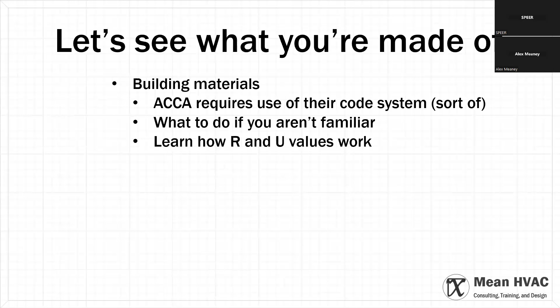So like I said, learn how U values work. Real simple, you just flip the number. R values and U values are inverse, or reciprocal, of each other. If I have the R value, remember from high school math, R over 1, or R divided by 1, is still just R. 2 divided by 1 is 2. So R over 1 equals 1 over U. You can flip that around and say, okay, I have the R value, I want the U value. Well, you take 1 divided by the R value, and that gives you the U value.